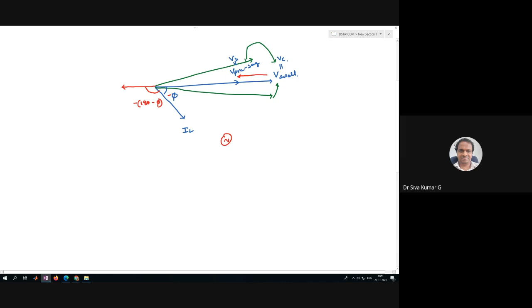With this angle, you can understand that the DVR or the series active power filter is going to take the real power as well as the reactive power. What I mean to say is that in order to mitigate the swell, the power flow will be in this direction, P plus jQ. It has to be taken from the source in order to decrease the voltage.